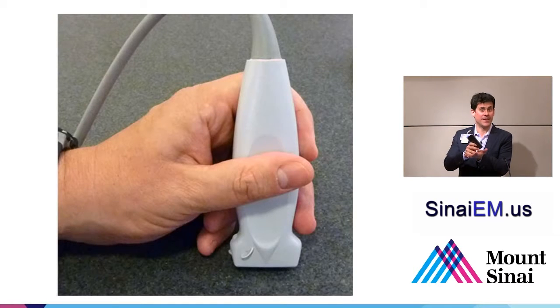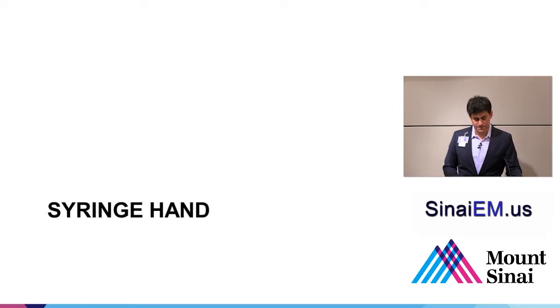This gives me a couple of different advantages. I'm not going to slide on this slippery gel-filled surface because I've got good probe stability, and also I can use the small muscles in my hand for a lot of fine motor control over exactly where I'm going to place the probe, so I can control how much pressure I'm going to put in a very fine fashion. So hold the probe in your hand, which is typically going to be your non-dominant hand, so that you're stable like this. You also want to keep most of your fingers behind the probe so that you're not getting in the way of the needle that's going to be getting very close to the base of this probe.